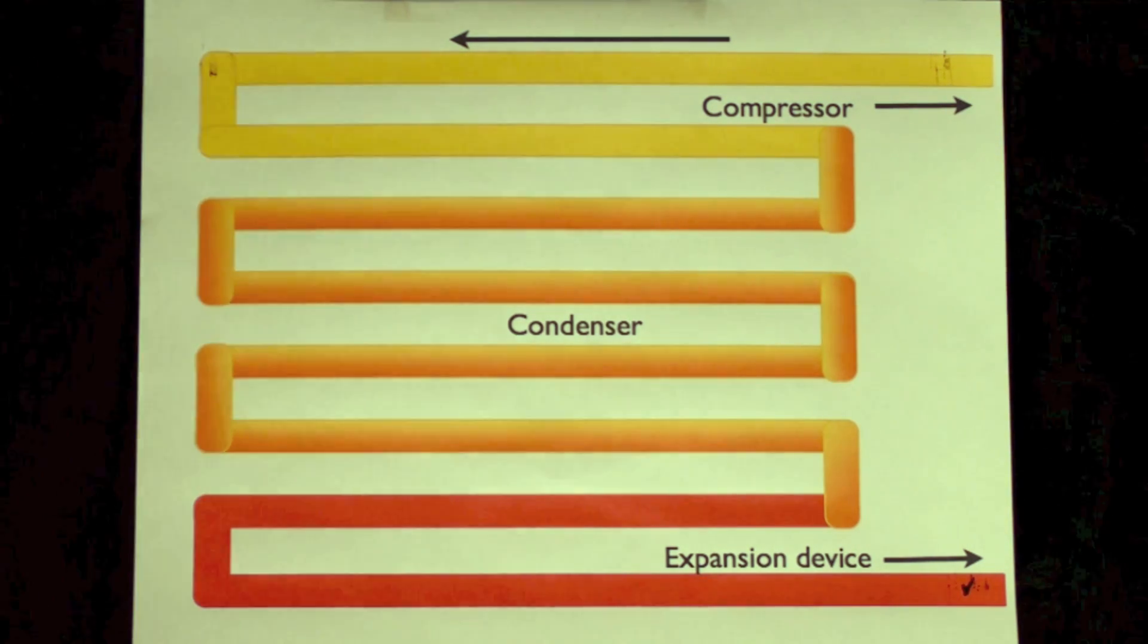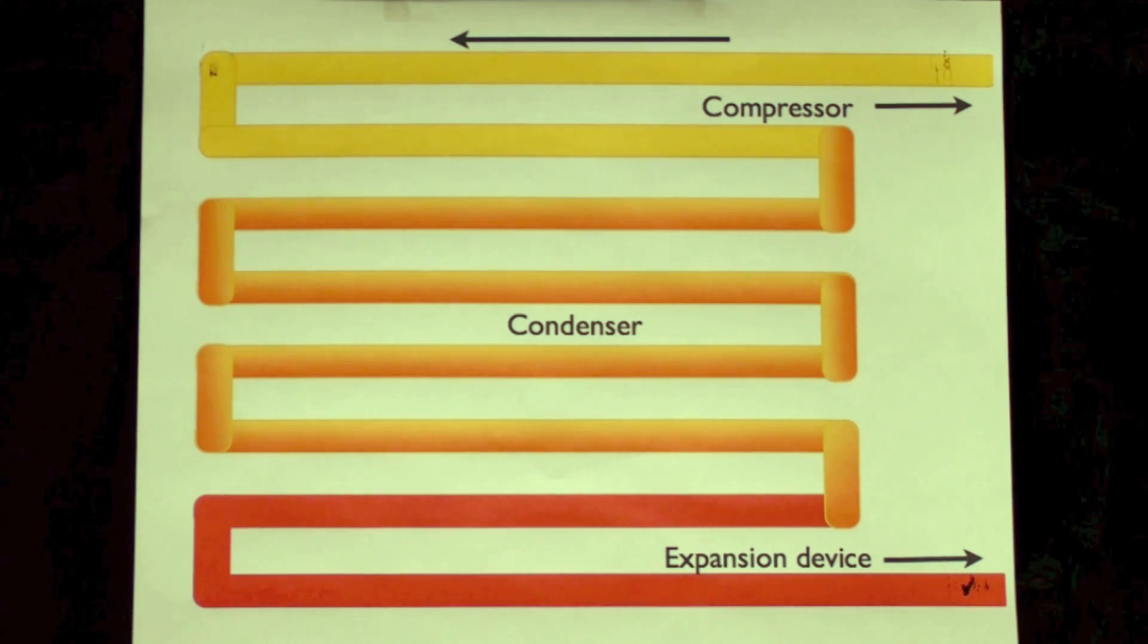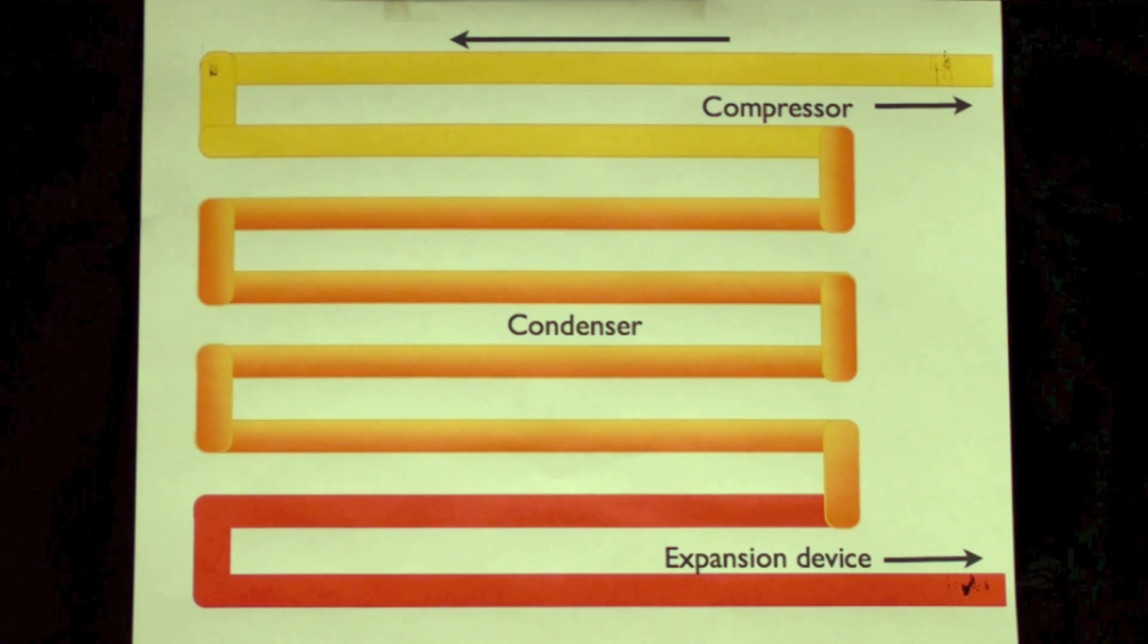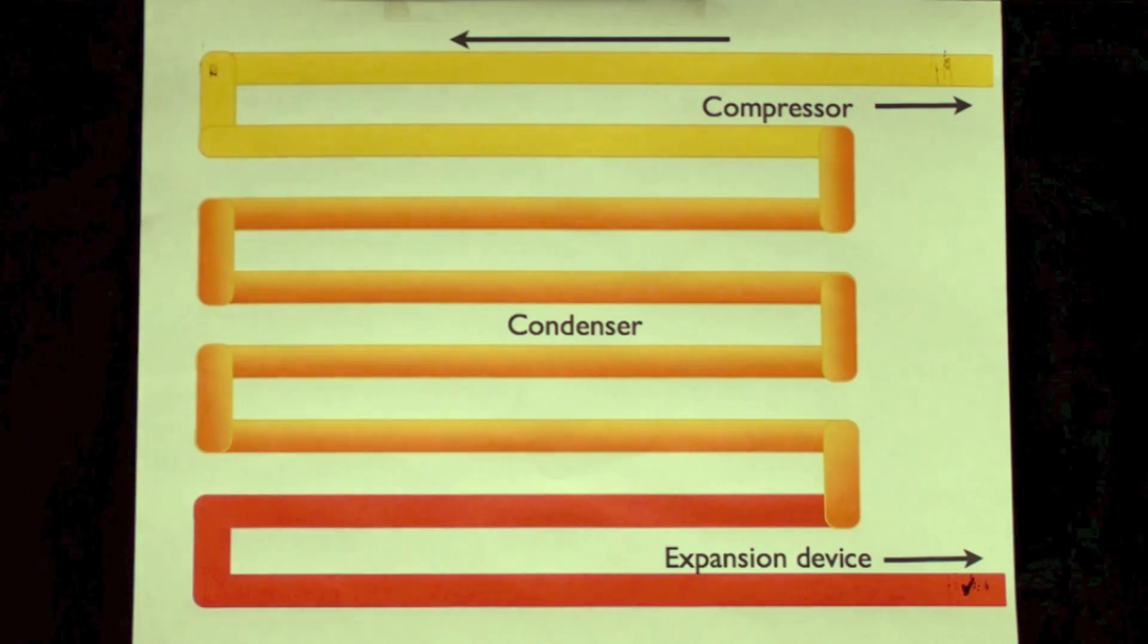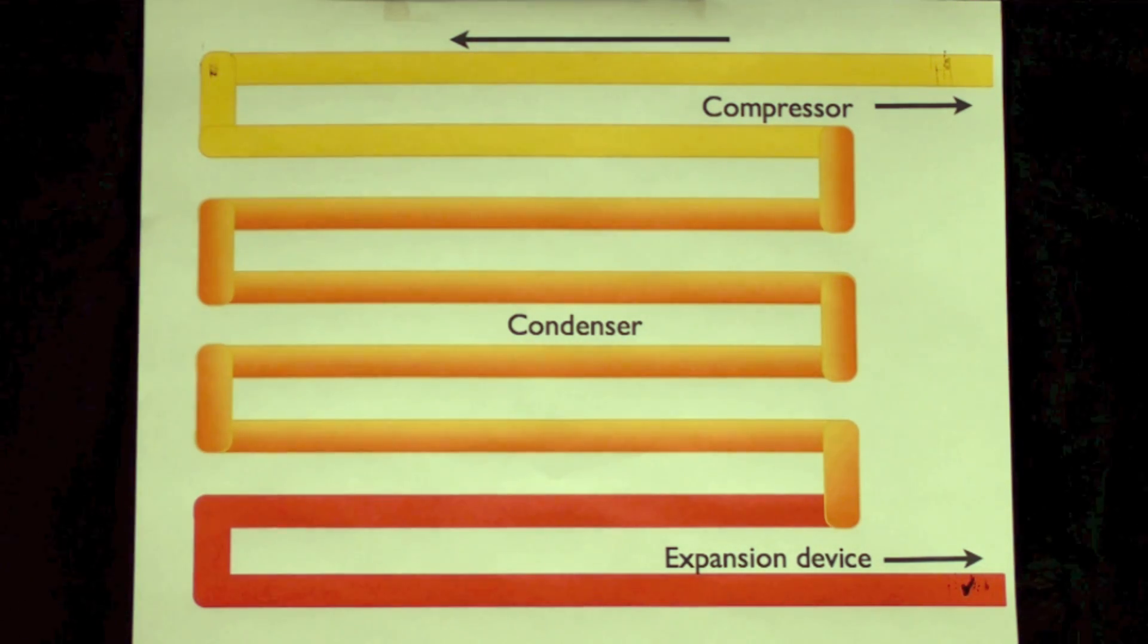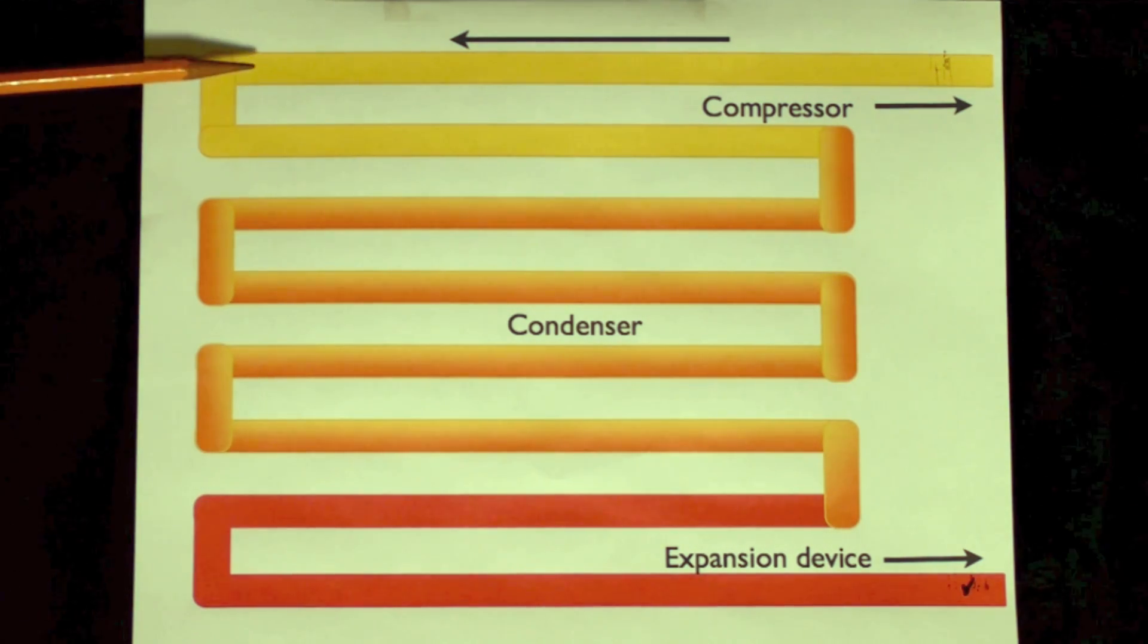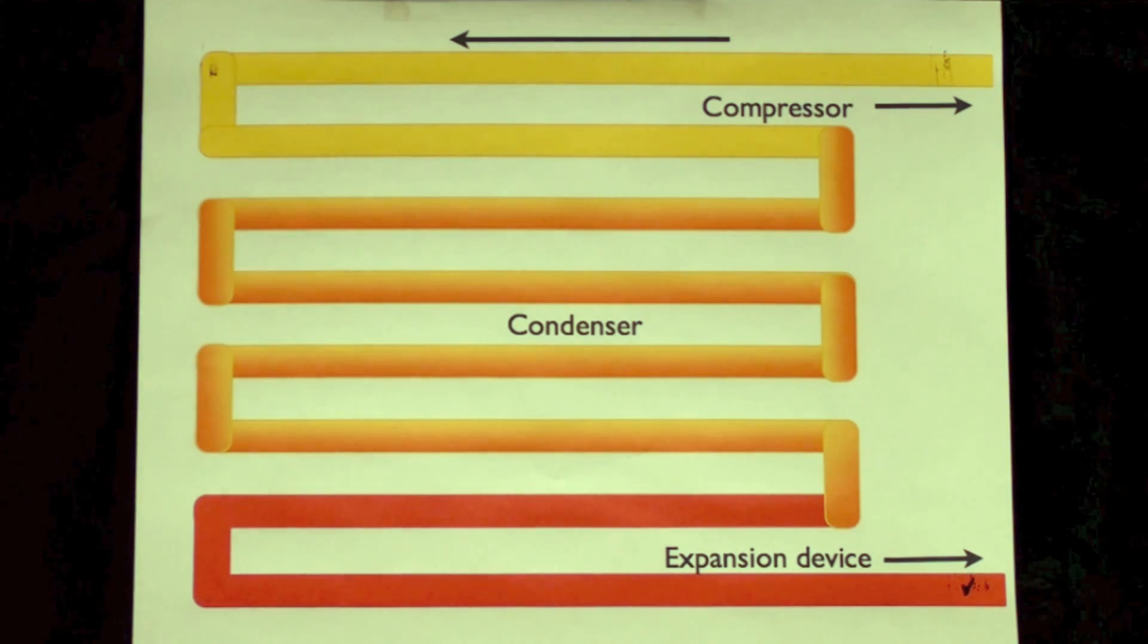One other thing on condensers: ideally a condenser would be about a quarter larger than the evaporator. In practice, it's really not done that way. But the reason being is when the compressor compresses the gas, it takes energy. That's why this gas is hot. This will usually burn you if you touch it as it comes out of the compressor.